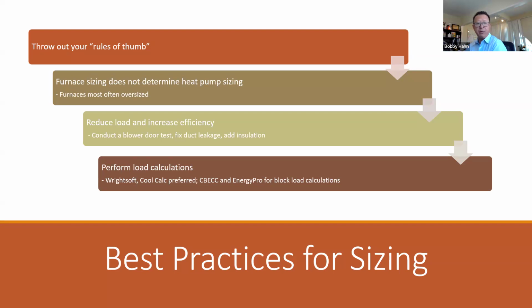Okay, so I'm going to end with this slide for my portion. Practices for sizing, rules of thumb, throw them all out. You are going to want to take a load calc for your application. Furnace sizing is not equivalent to heat pump sizing because most furnaces are oversized, so you don't want to go match to match. You again want to do a load calculation. You're going to have increased efficiency with the reduced load.